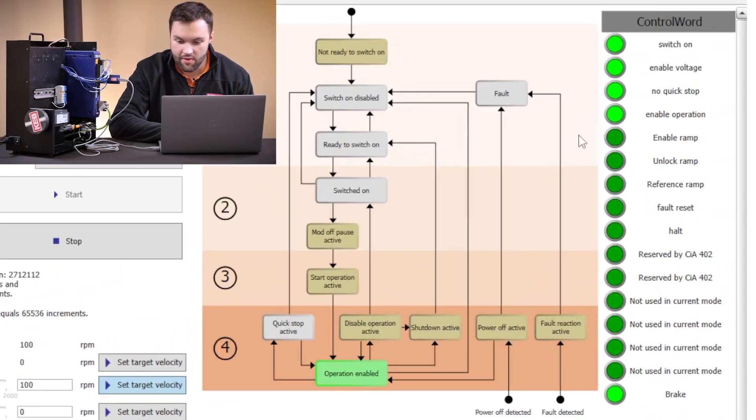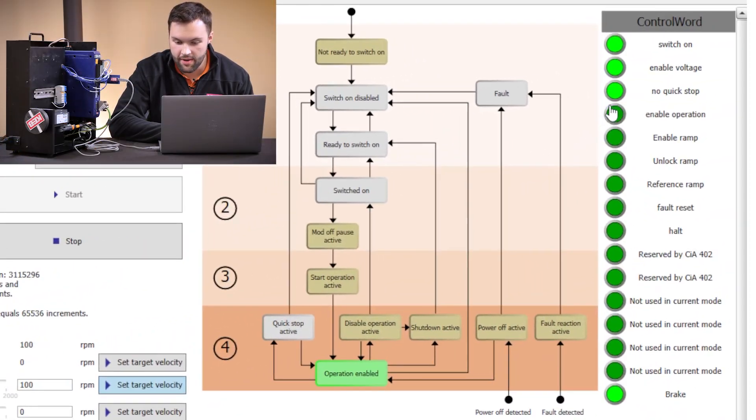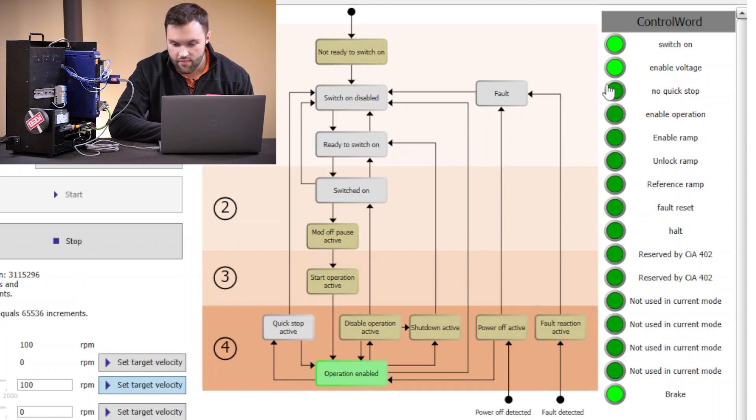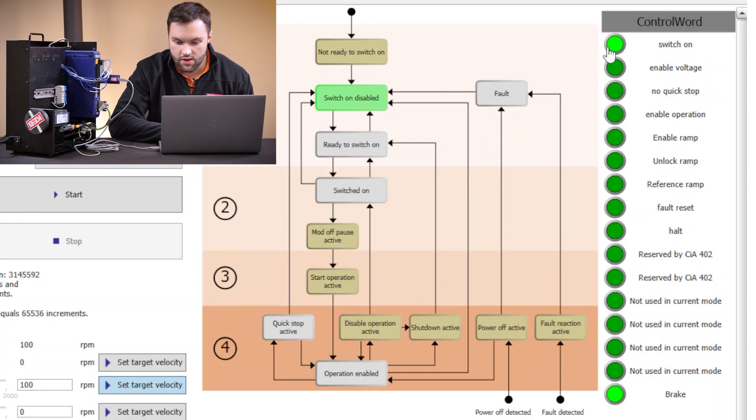Then as soon as I want the motor to stop, if I want to disable operation, I can drop the enable operation bit, drop no quick stop, drop enable voltage, and drop switch on.